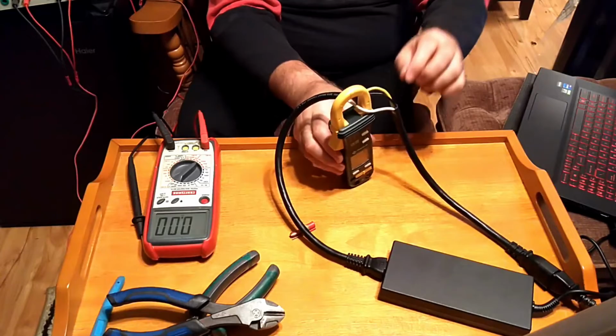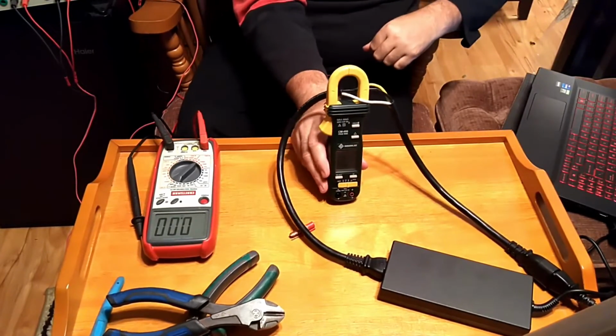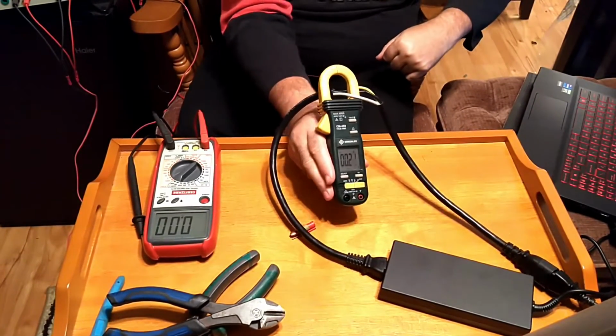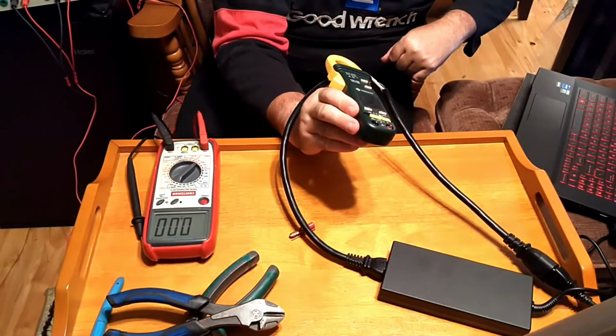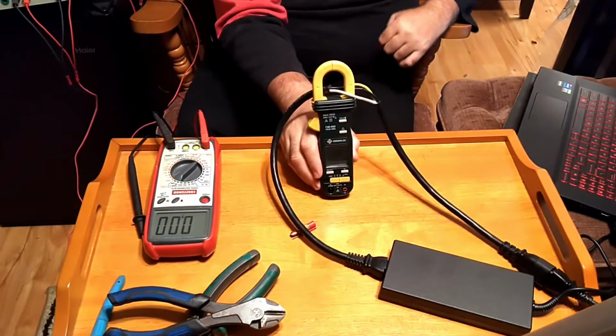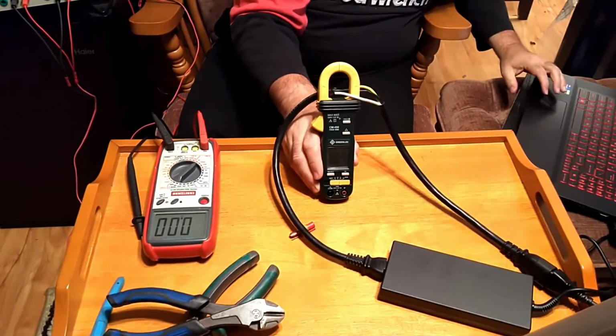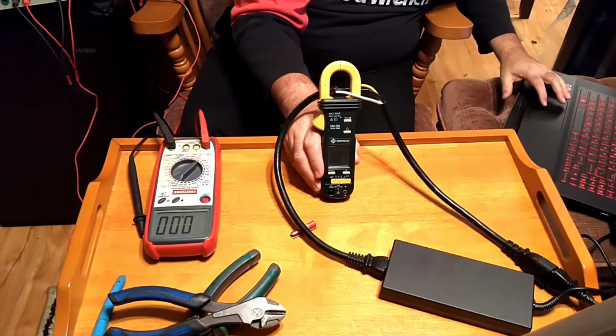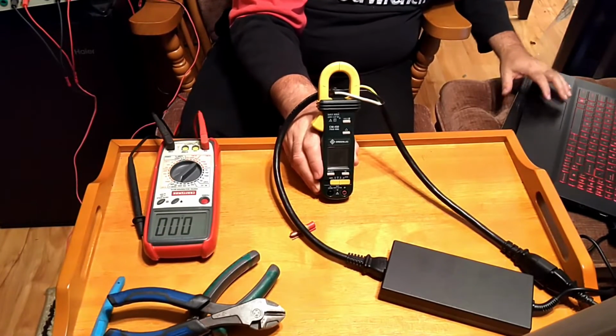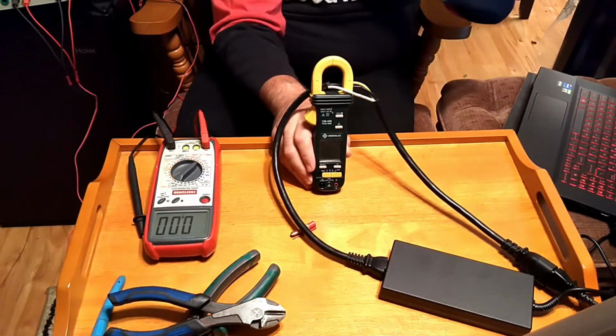Because current's flowing in one direction, it's looping through the load and coming back, flowing back through the other direction. So you've nulled out your reading because current through one end must be the same as current coming back through the other end. So you've got nothing. This is reading 0.3, which is just spurious.